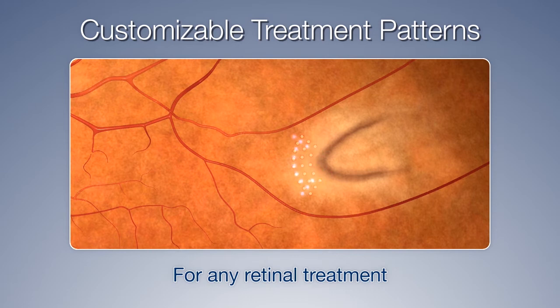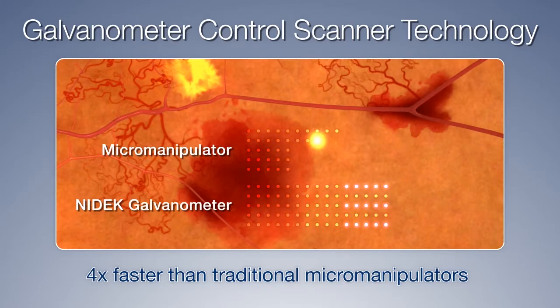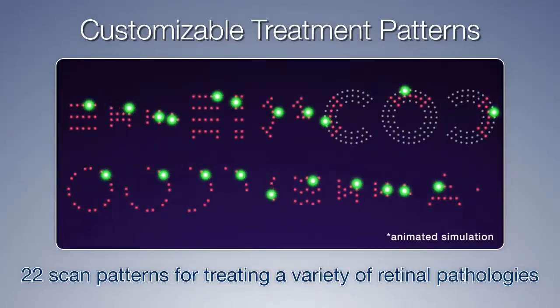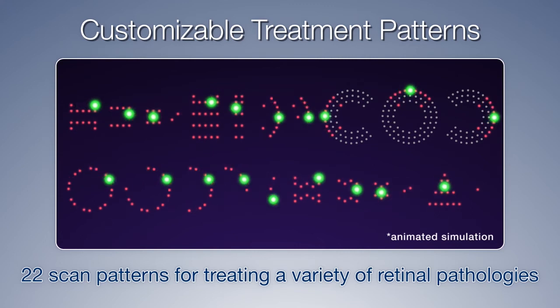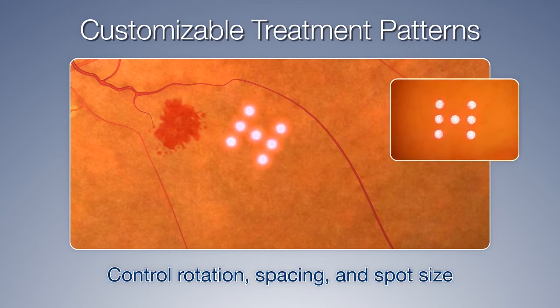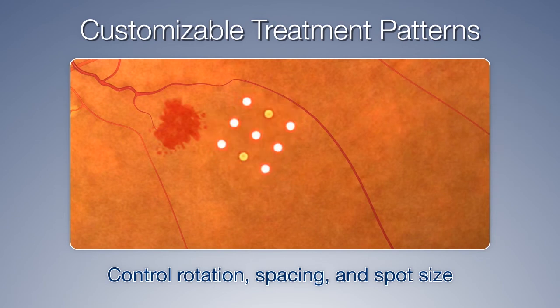and retinal holes or tears. NIDEK uses galvanometer control scanner technology, which works four times faster than traditional micromanipulators. The laser includes 22 pre-programmed scanning patterns that can be easily customized for treatment of a variety of retinal pathologies. The MC500 VIXI offers more scanning patterns than ever before, with adjustable spot spacing for precise treatment and continuous variable spot size control for better burn titration.